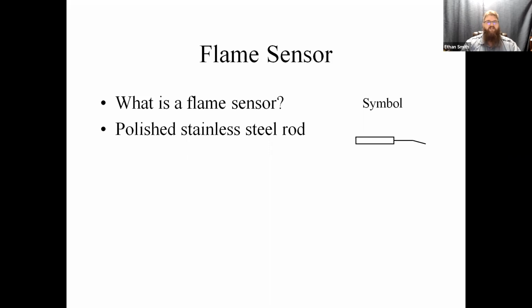Seven, eight service calls a day, that can get pretty pricey. So what we want to do is use something that's just going to take the crap off of the flame sensor, but not touch the polish on the flame sensor. So things like double or triple aught steel wool work. Steel wool makes kind of a mess in your bag when it gets wet, so I generally don't recommend that.